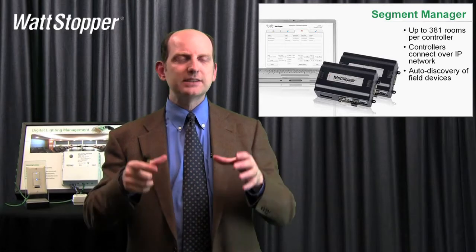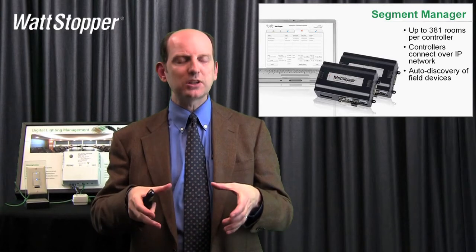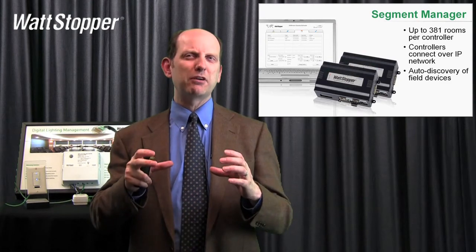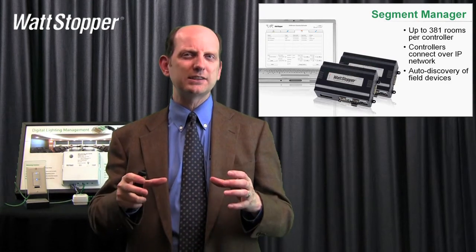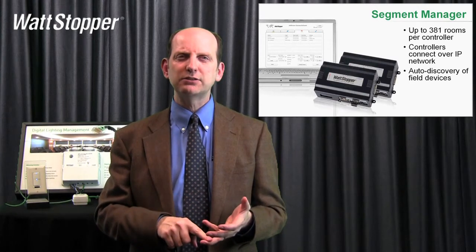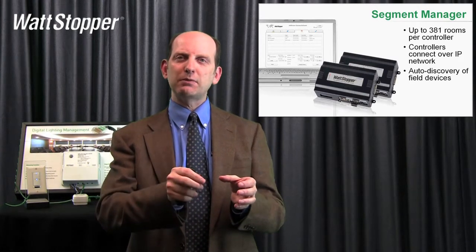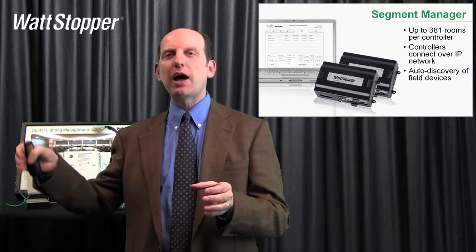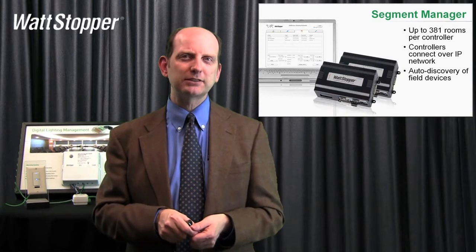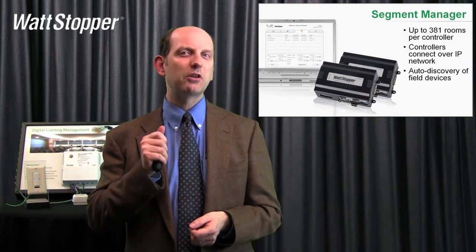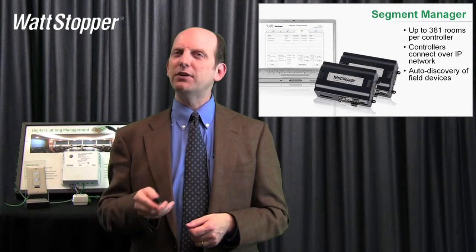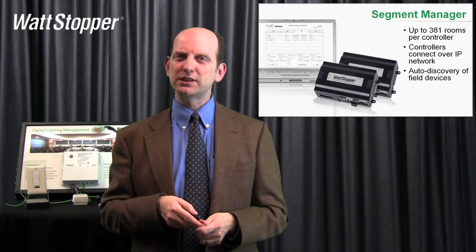The segment manager is basically an interface device — almost like a little mini computer inside a plastic device built for a rigorous environment. It's a server-class device that goes into, let's say, an electrical closet or an HVAC room. From one segment on that device we can go out to up to 127 rooms. We have a segment manager that has three individual segments, so those three segments can go up to a total of 381 rooms. That's more control than most facilities would ever need.